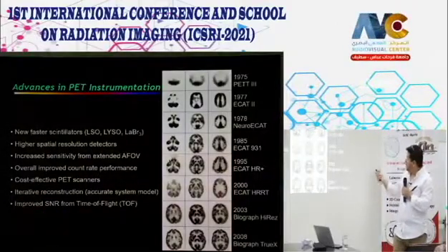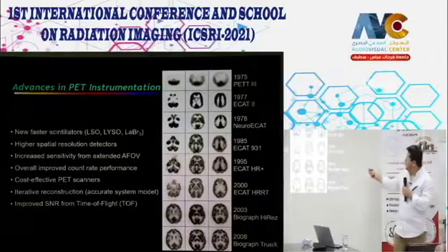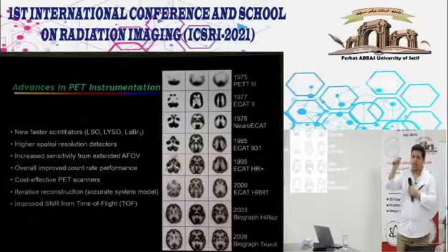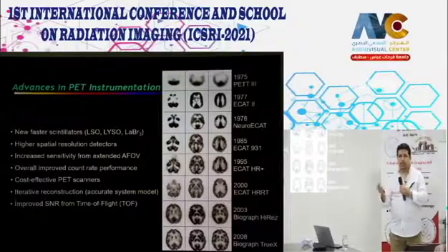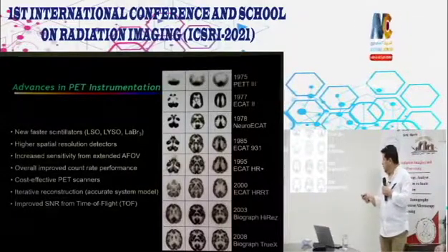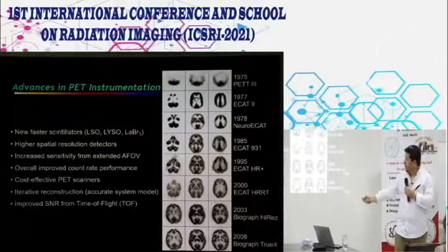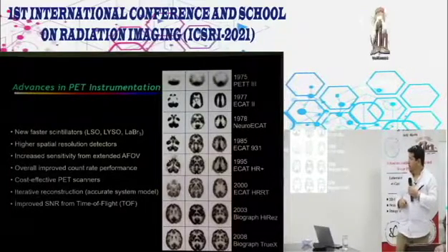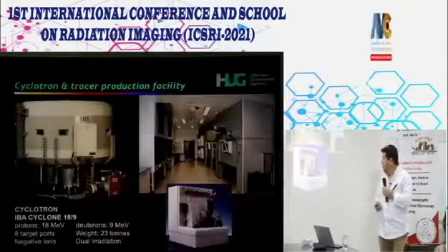And here you basically see the evolution of the quality of PET images for the brain. You can appreciate the low resolution in the first design of the 70s. Pixel size was close to 1 centimeter, so very low spatial resolution. And now the spatial resolution is close to 2.5 millimeters. So we can image organs at very high spatial resolution, taking advantage of what you see here: scintillation crystals that have a higher stopping power, fast electronics, advanced reconstruction techniques, and so on and so forth.